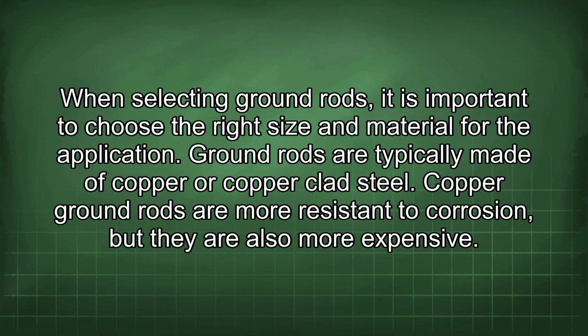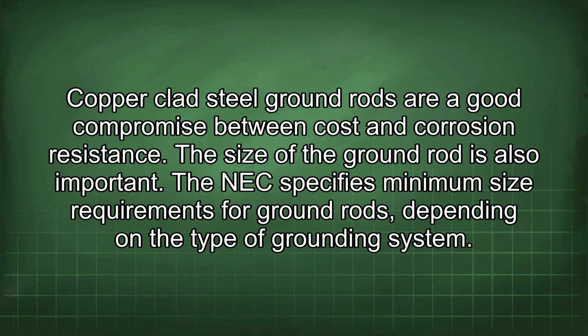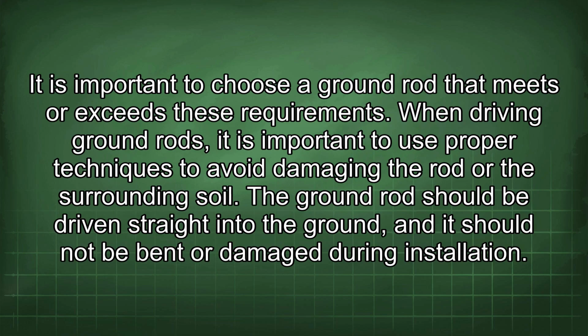When selecting ground rods, it is important to choose the right size and material for the application. Ground rods are typically made of copper or copper-clad steel. Copper ground rods are more resistant to corrosion, but they are also more expensive. Copper-clad steel ground rods are a good compromise between cost and corrosion resistance. The size of the ground rod is also important. The NEC specifies minimum size requirements for ground rods, depending on the type of grounding system. It is important to choose a ground rod that meets or exceeds these requirements.